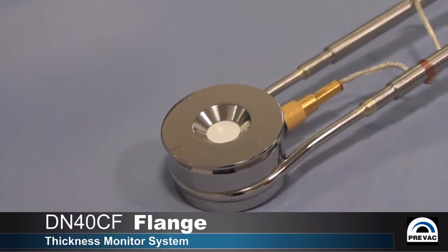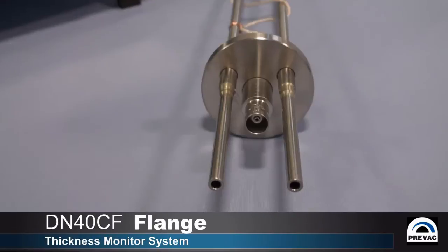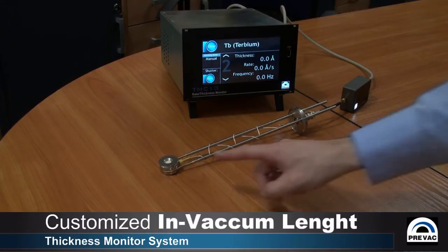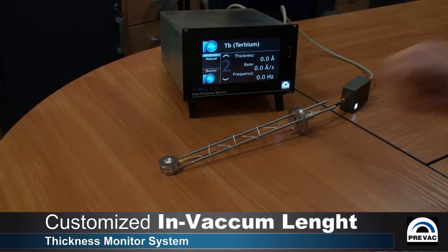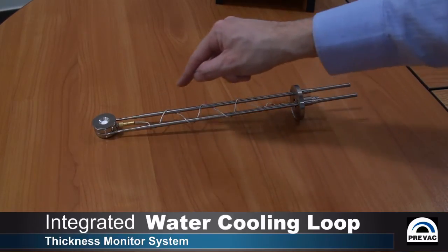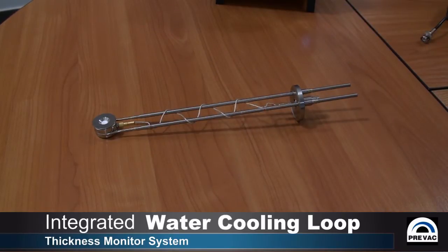In the standard configuration, the quartz balance oscillator is mounted on a DN40CF flange. The in-vacuum length or insertion length can be customized according to the application and the dimensions of the vacuum chamber.